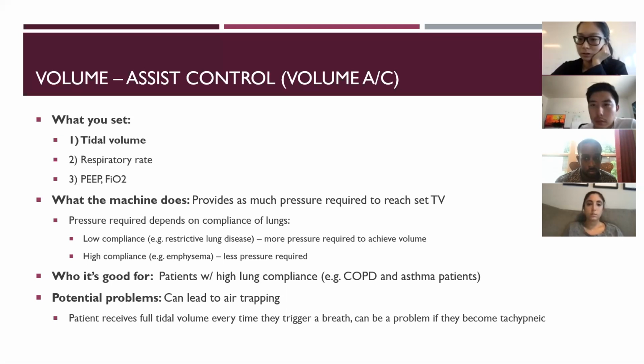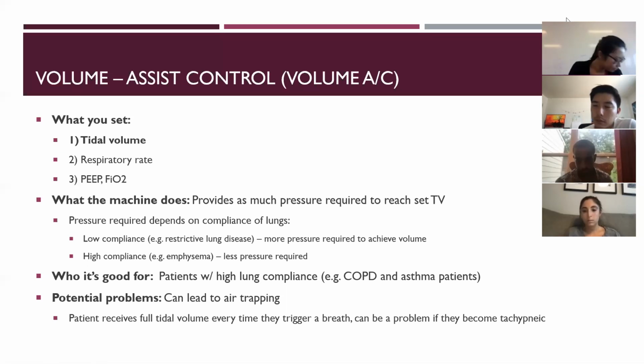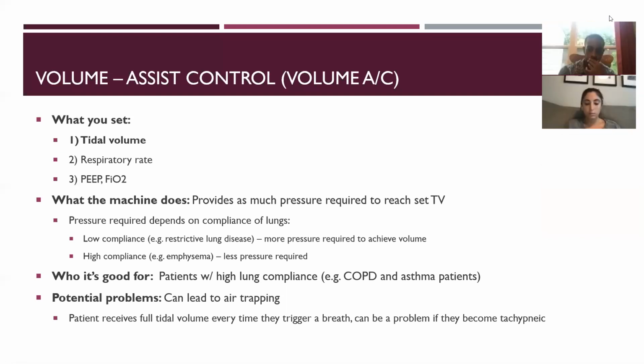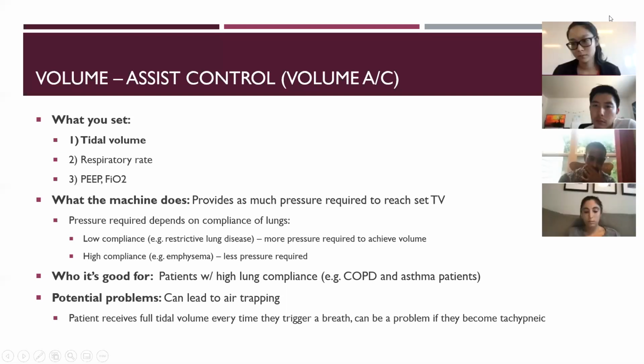Let me just jump into, I'll come back to that. Is that okay? Ventilators have two ports, inhalation and exhalation ports. And in both of them, there is a trigger sensor for pressure and there is one for flow. As was said, there's literally a setting on the ventilator where you say flow trigger of this many liters per minute, I want to give the breath. So the ventilator is constantly listening, and as soon as it hears that the patient is triggering the vent, meaning trying to inhale and create a flow that is not generated by the machine, it understands that the patient is trying to breathe. Make sense?